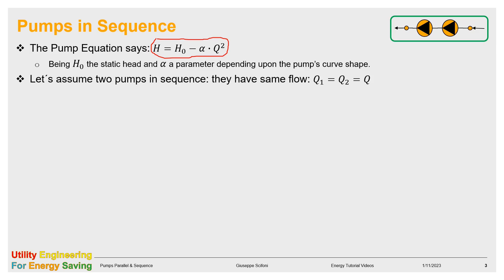Let's start from the sequence operation. The equation of the centrifugal pump says the head as a quadratic function of the flow, being a descending parabola. This function depends upon two parameters: the static head H₀, that is the head at zero flow, and the curve shape α. Those parameters are given. We will see later on that α can be experimentally found.